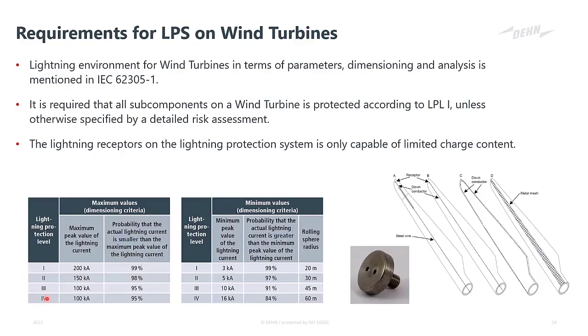In a level 4, the system will start detecting or protecting from 16 kiloamps, and it will protect up to 100 kiloamps. In a level 1, it will start protecting from 3 kiloamps up to 200 kiloamps. So the band doesn't just increase on the higher side, it also gets closer to 0, so the band widens. We'll also look at smaller peak value strikes, so we don't miss small strikes.